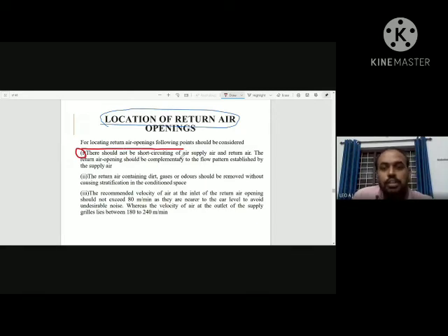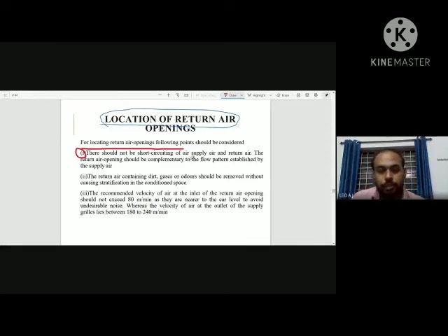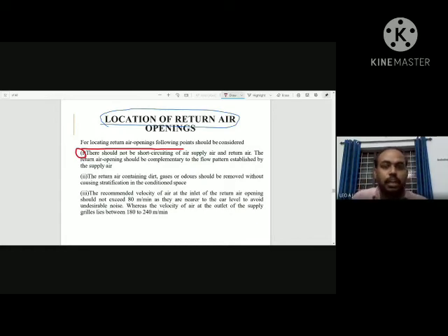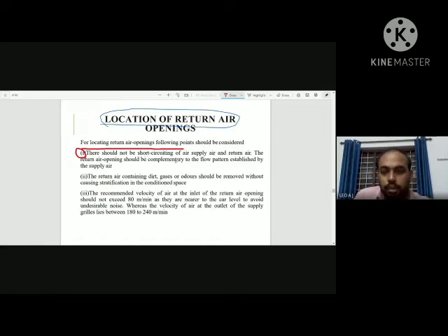The first principle: there should be no short-circuiting of air. Supply air and return air should not mix directly. If supply air goes directly back to the return air without circulating through the room, there is no conditioning effect. There should be no direct mixing between supply air and return air to avoid short-circuiting.